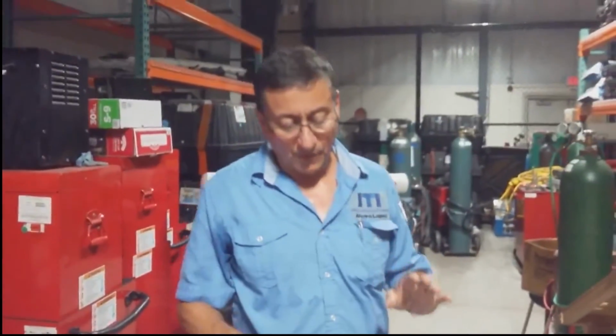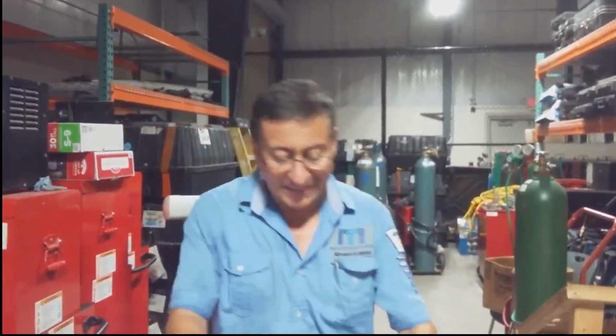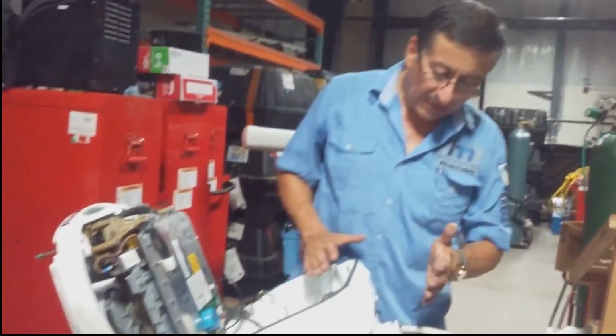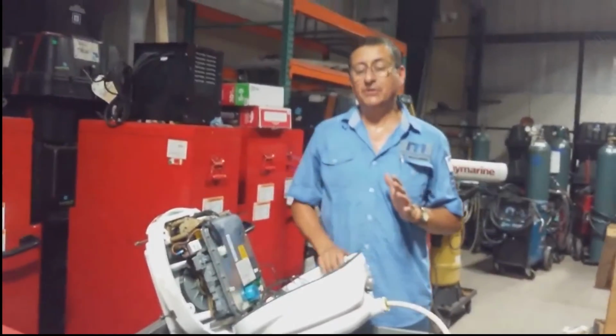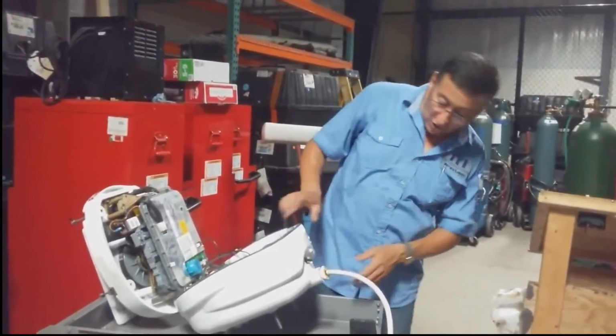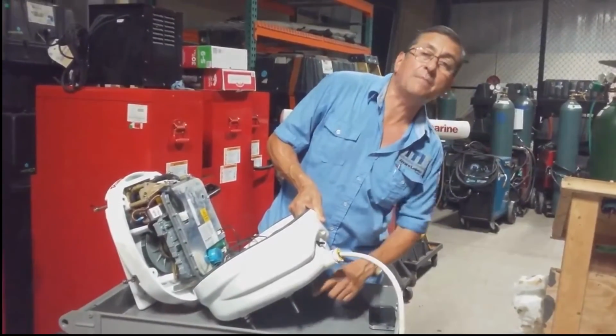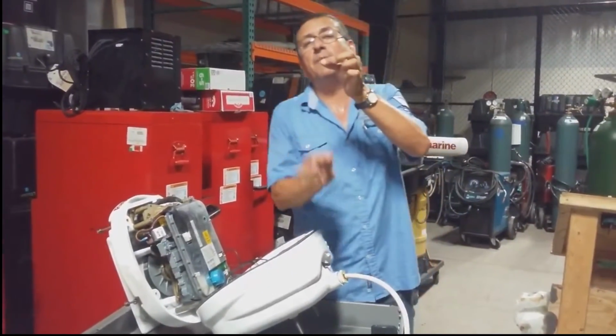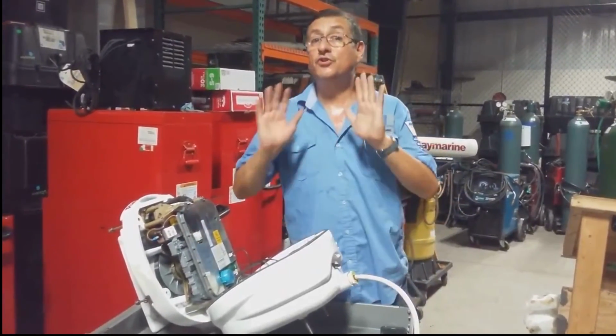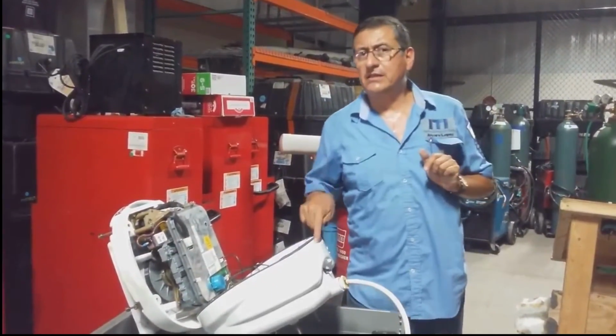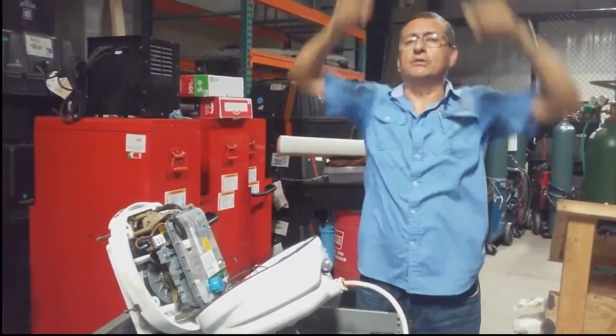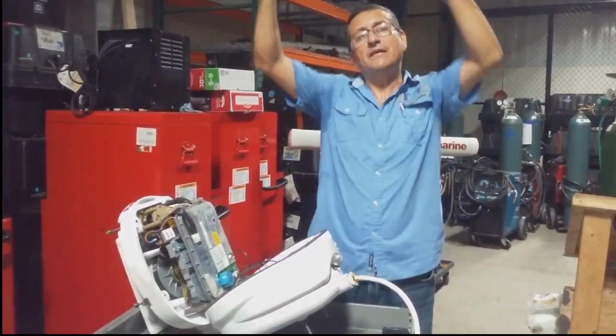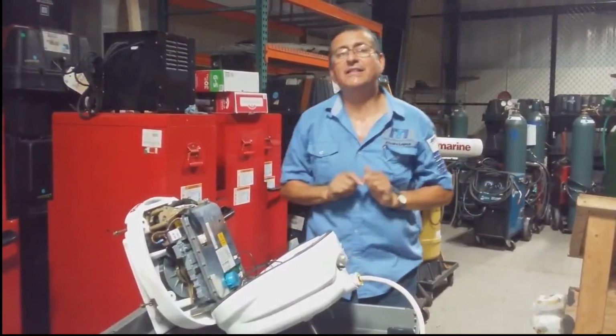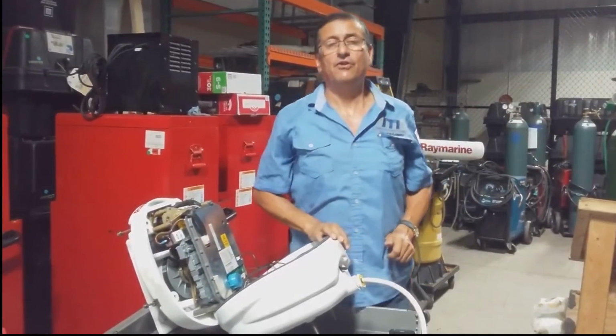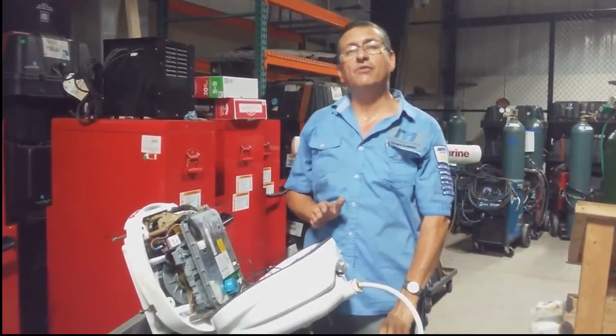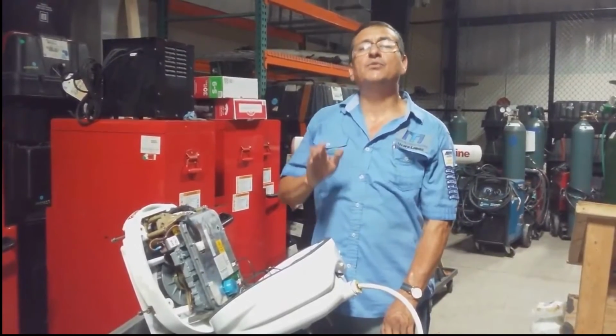Very important recommendation. Another important recommendation is that this case should be properly isolated, or if necessary, connect one of the bolts in the bottom to the bonding system in order to avoid future problems. Why? Where is that equipment located? On top of the boat. If you don't have the rod appropriately installed, this one is your draining. For that reason, I recommend connecting the body of this equipment directly to the bonding system.